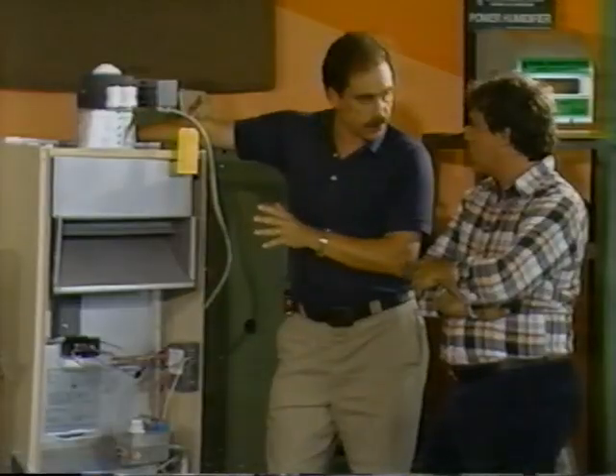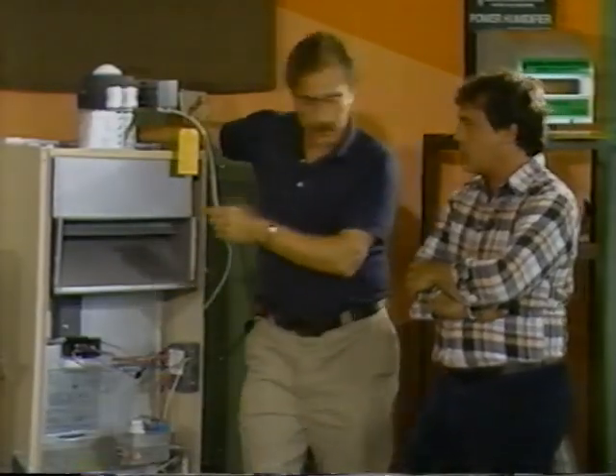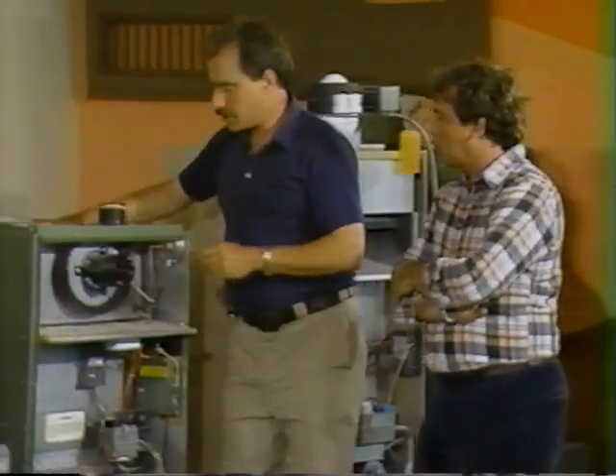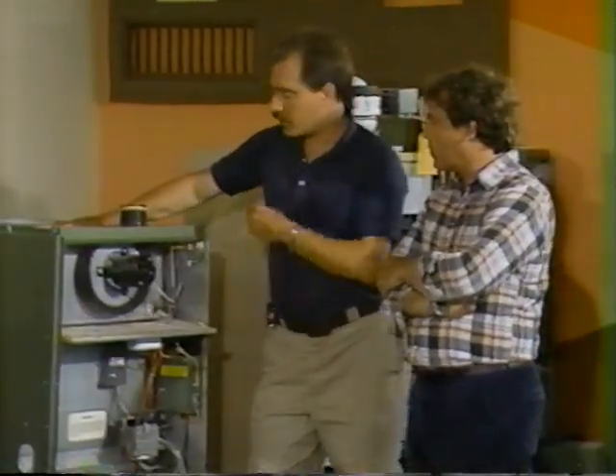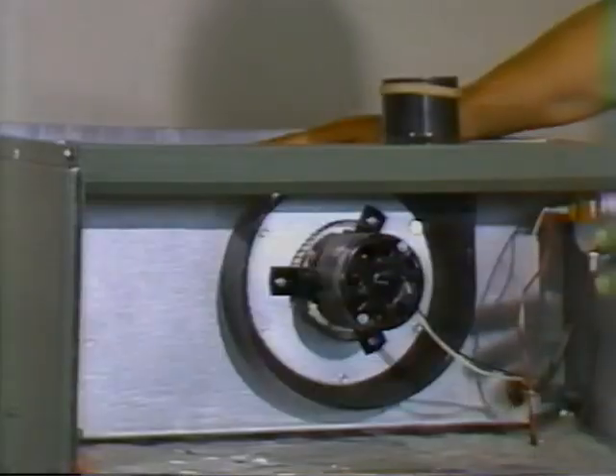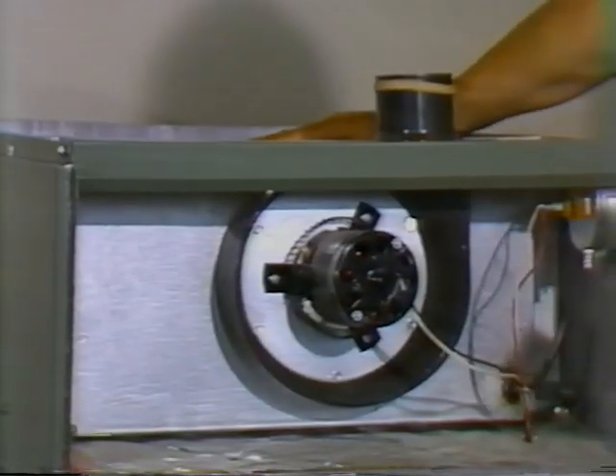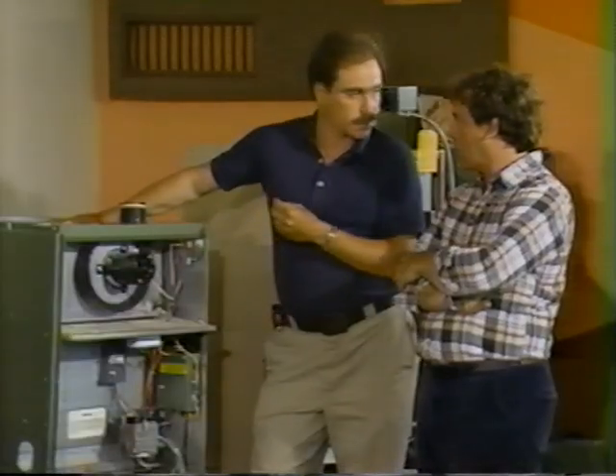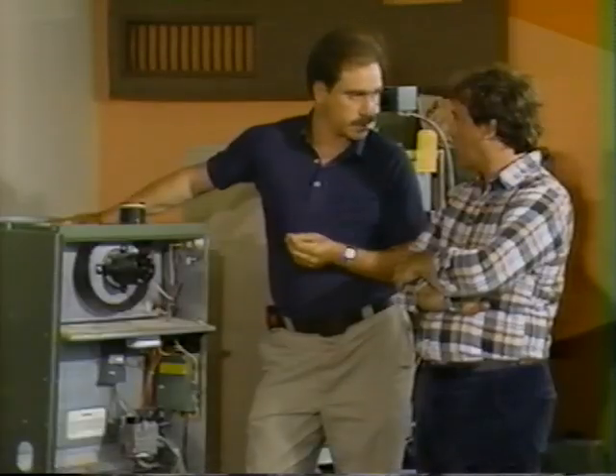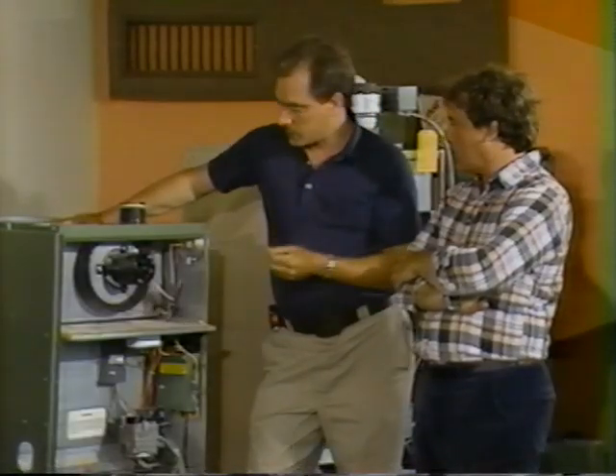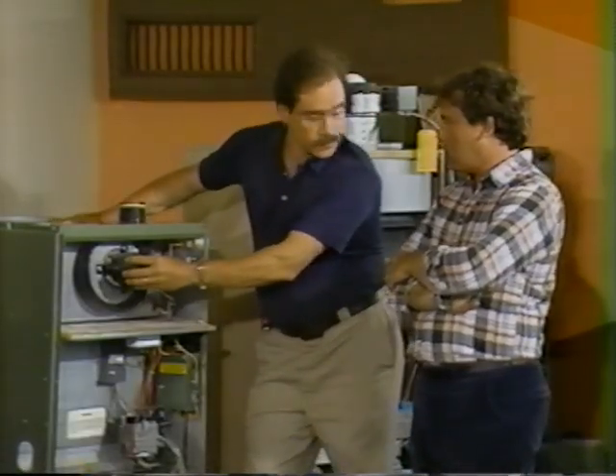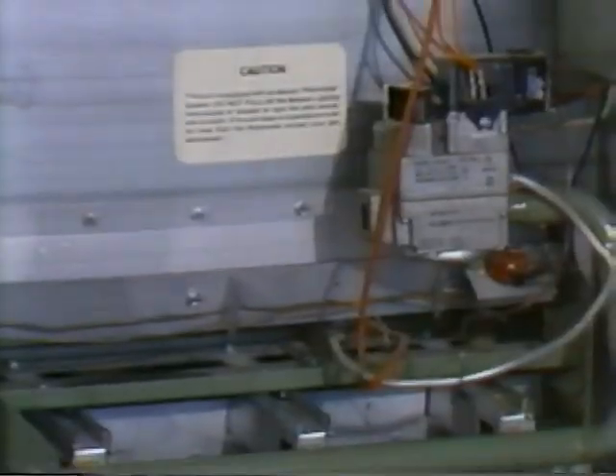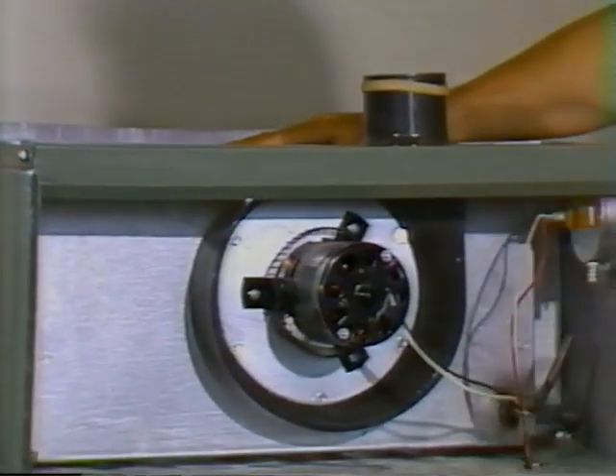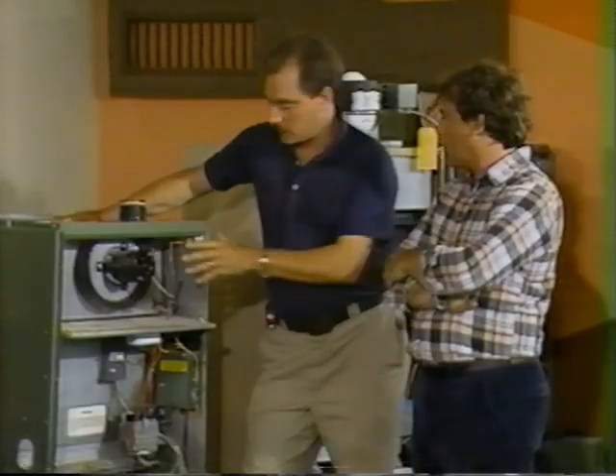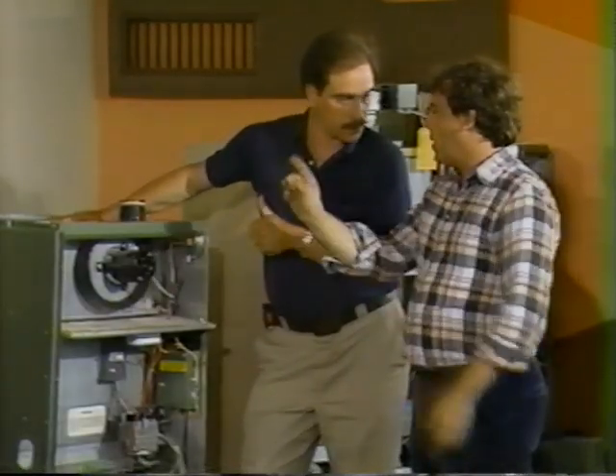Look at the size of the heat exchanger here and compare it to the next unit we're going to look at. The heat exchanger in this unit is enlarged, which means that the flue gases are cooler. It is a more efficient unit. Efficient enough so that it is impossible to rely on the stack effect to exhaust the products of combustion. As a result of which, we've put a blower in this unit, which actually induces the draft and ensures that that takes place. This is very appropriate for an energy-conserving house because there's no way you can backdraft it. The blower will ensure that the flue gases are leaving the building.